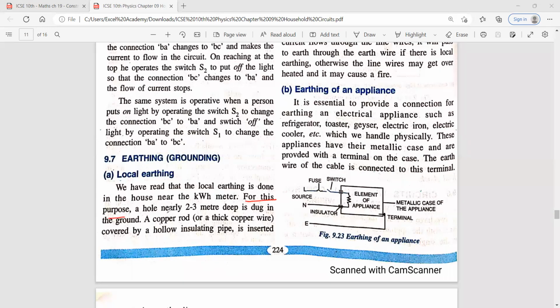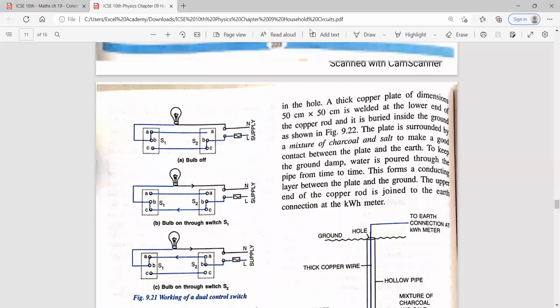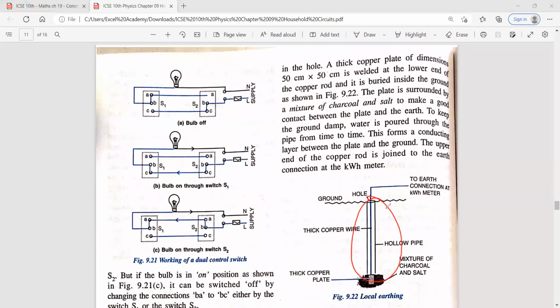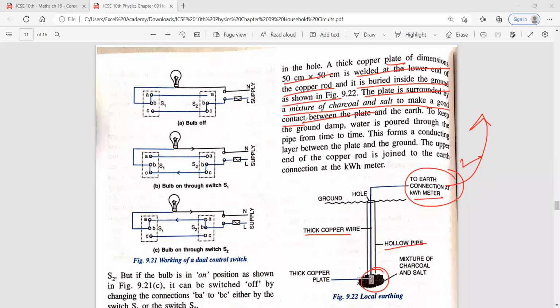For this purpose, a hole nearly 2 to 3 meters deep is dug in the ground when the building is being constructed, when the foundations are laid. A copper rod or a thick copper wire covered by a hollow insulating pipe is inserted in the hole. You can see here, this hollow pipe, and inside it the thick copper wire is inserted. This is connected to the kilowatt-hour meter, but that doesn't matter. Every socket has this wire basically, and those are taken to the kilowatt hour meter, and from there to the earth. A copper plate of 50 by 50 centimeter is welded at the lower end of the copper rod, and it is buried inside the ground as shown in the figure. The plate is surrounded by a mixture of charcoal and salt to make a good contact between the plate and the earth.